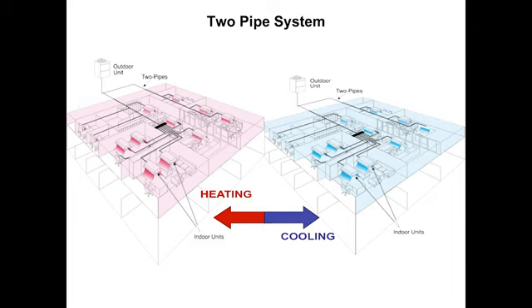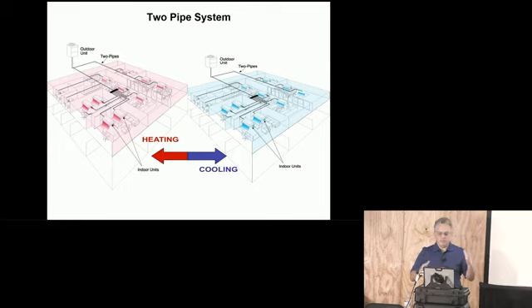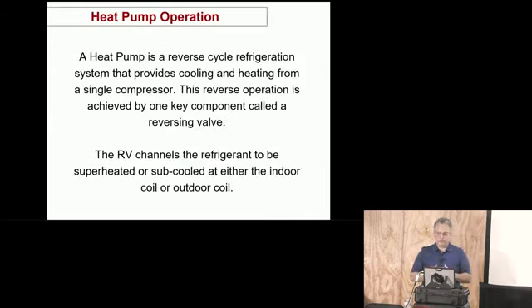So you have one mode at a time. Typically, first mode wins. There are a lot of strategies to manage the mode call. We're not going to go over that today, but there are. But generally speaking, first mode call wins. So if somebody gets there in the morning or turns on heat, then it's going to be heat until specific criteria is met for it to do system changeover. So a heat pump is a reverse cycle refrigeration system that provides cooling and heating from a single compressor. The reverse operation is achieved by one key component called the reversing valve. The reversing valve channels the refrigerant to be superheated or subcooled at either the indoor unit or the outdoor unit.